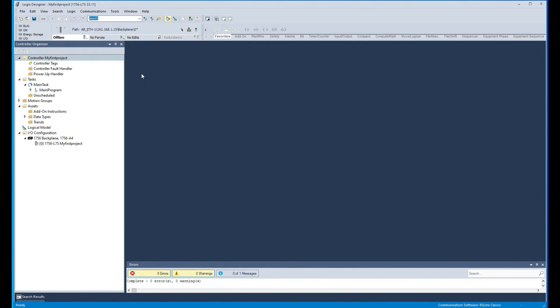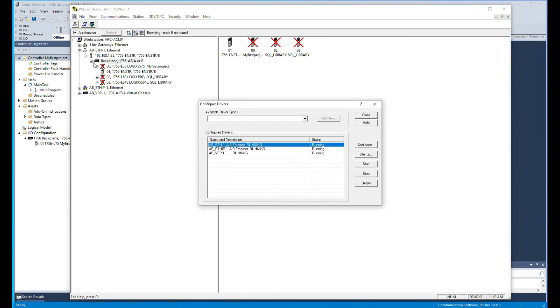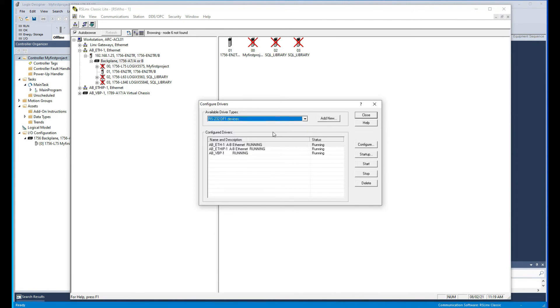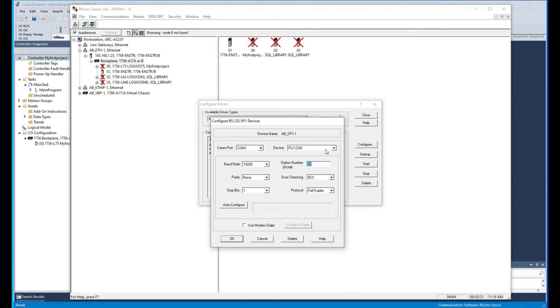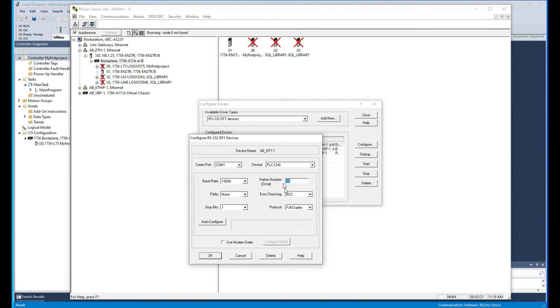Just to show you that, I am going to just go offline with that like this. I'm going to plug here the serial. So with the serial communication what you want to do is you go to RSLinx again and then you click on the drivers here, and then we're going to pick the RS232 DF1 devices. So the DF1 is the native protocol for Rockwell.